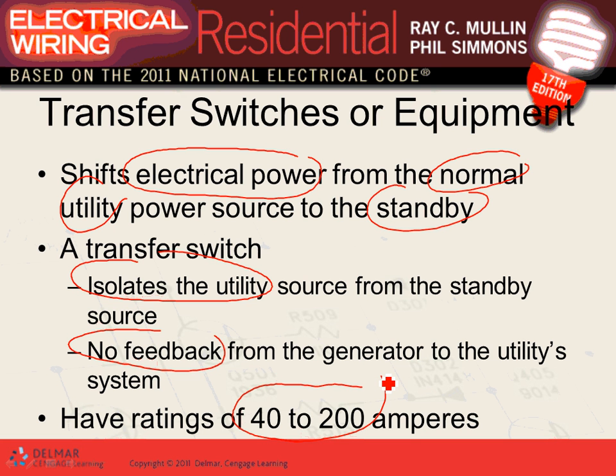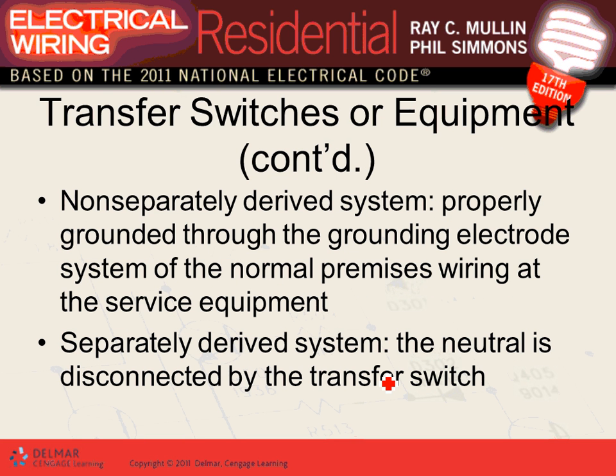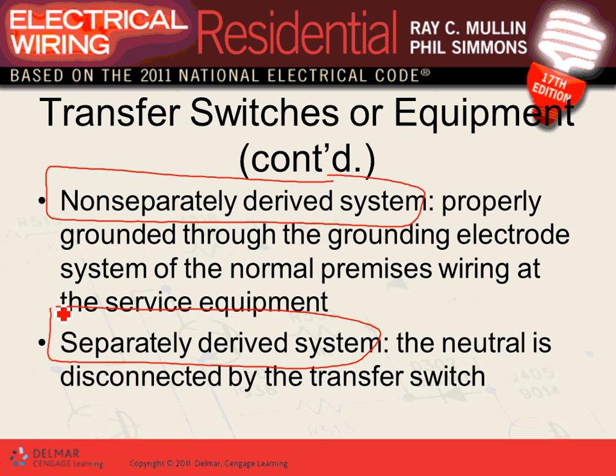What happens, guys, if you start your generator and you're feeding power, and you don't disconnect yourself from the grid, and the grid is down, is you send power through the transmission line and you could hurt somebody who's working on the transmission line. So that's why they want you to isolate yourself from the grid when you run. Okay, there are two terms that you guys are going to be familiar with: non-separately derived system and separately derived system. If you understand it now, Karen, you're good to go for the whole year, because we're going to be talking about it.